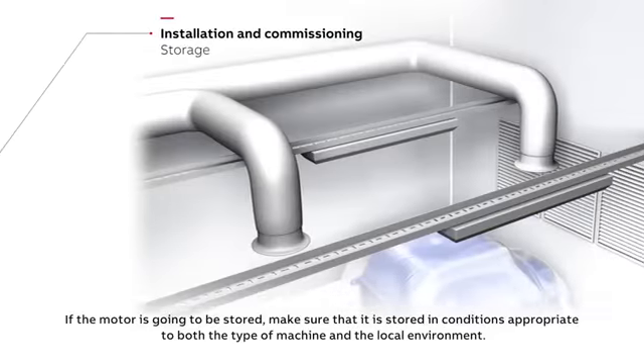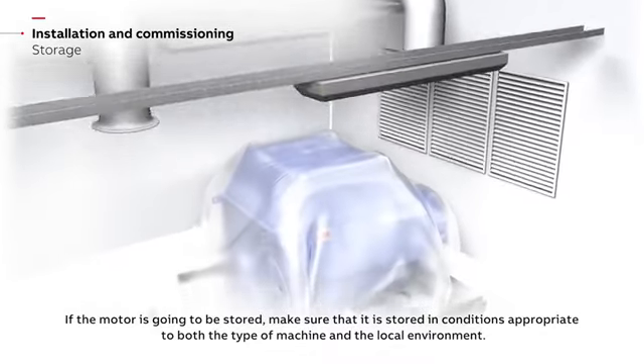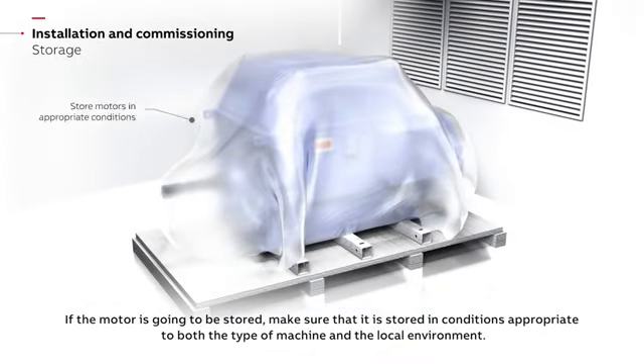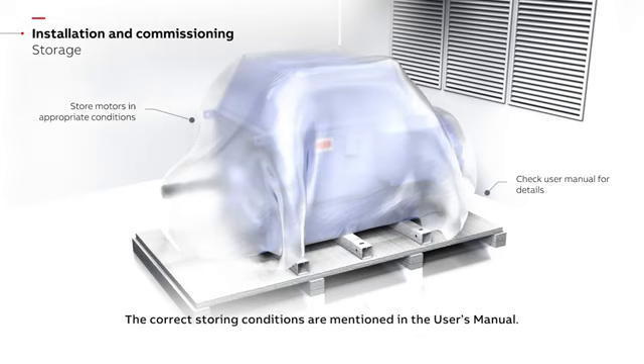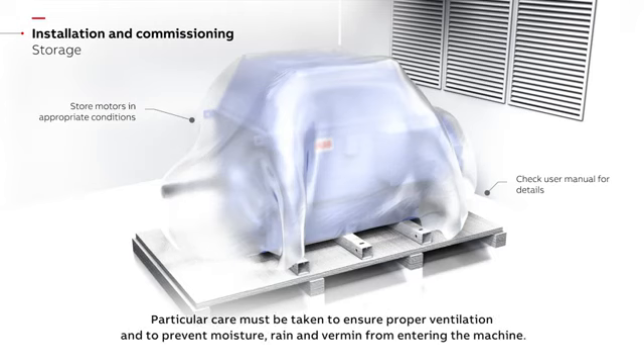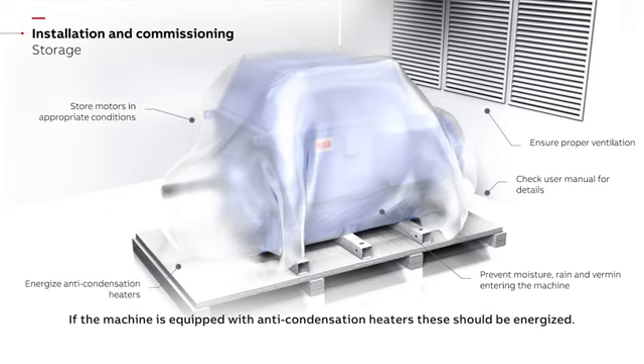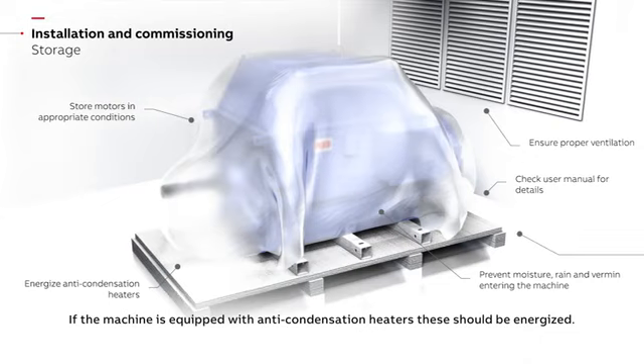If the motor is going to be stored, make sure that it is stored in conditions appropriate to both the type of machine and the local environment. The correct storing conditions are mentioned in the user's manual. Particular care must be taken to ensure proper ventilation and to prevent moisture, rain, and vermin from entering the machine. If the machine is equipped with anti-condensation heaters, these should be energized.